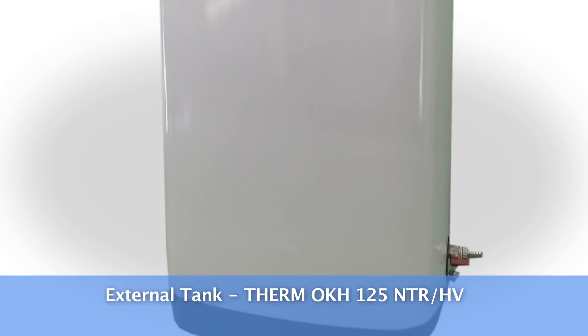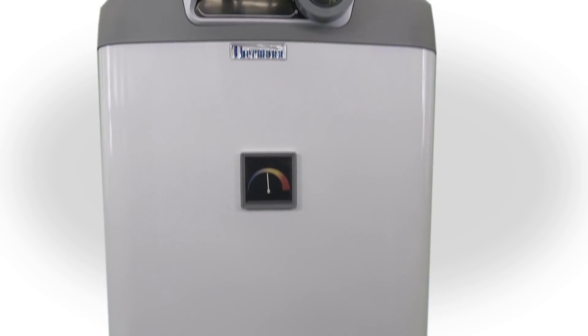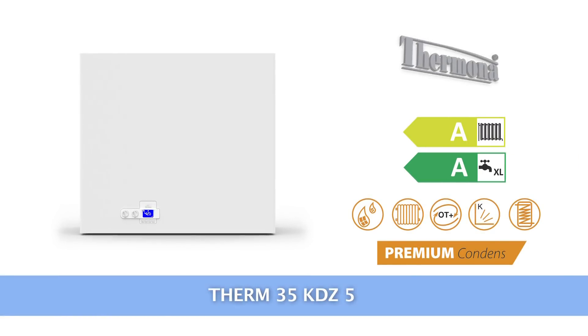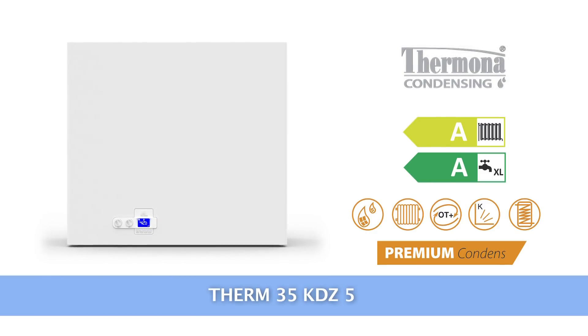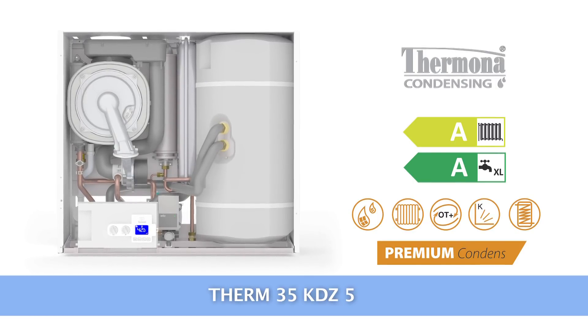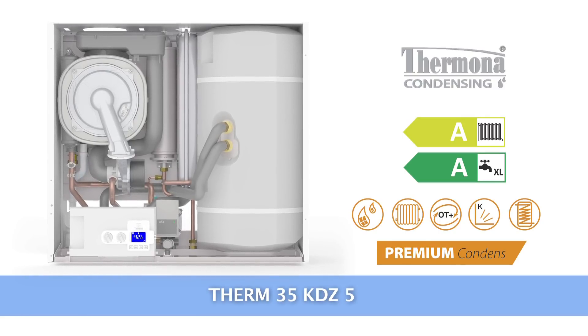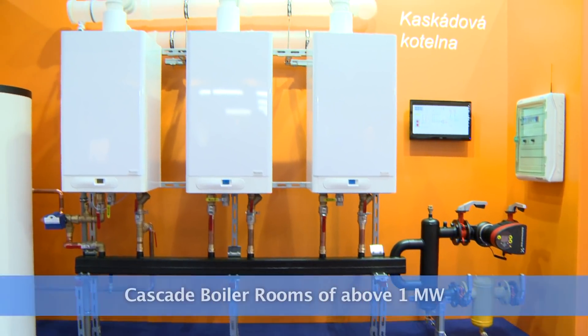The most common types of tanks are Therm OKH-100 and Therm OKH-125. The tanks have upper outlets and allow simple and compact installation under a wall-mounted boiler. Another type is the Therm 35 KDZ-5, with the water being heated in an inbuilt 55-litre stainless steel tank. This boiler can be used anywhere where outlets and interconnections between the boiler and the tank need to be covered, especially in the interiors of flats or small houses without utility rooms.